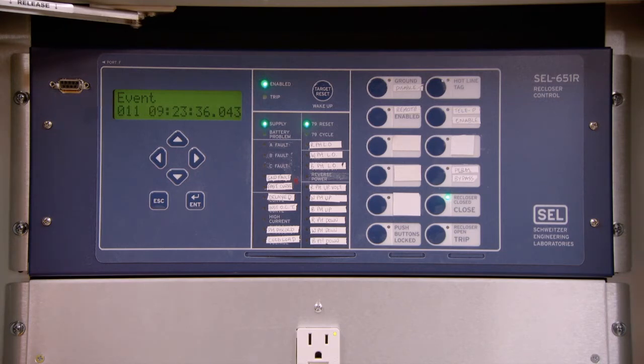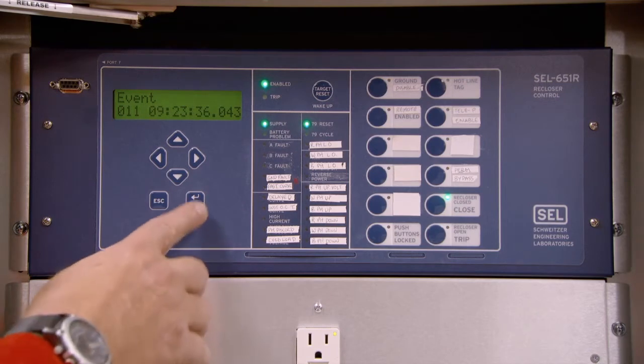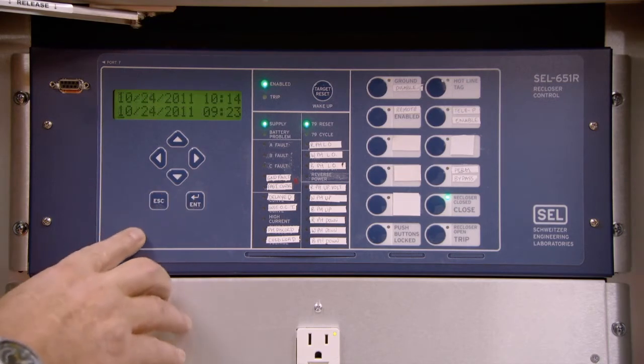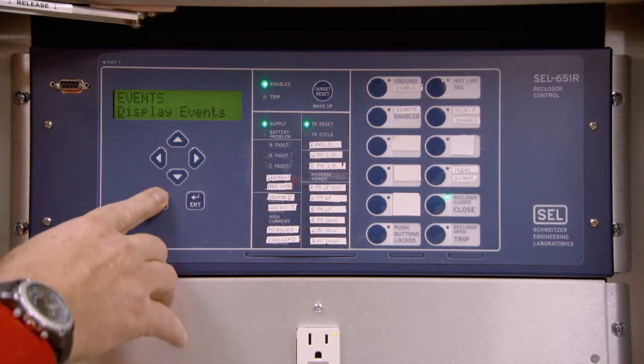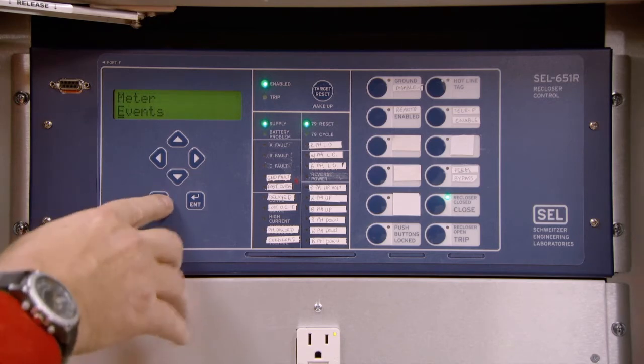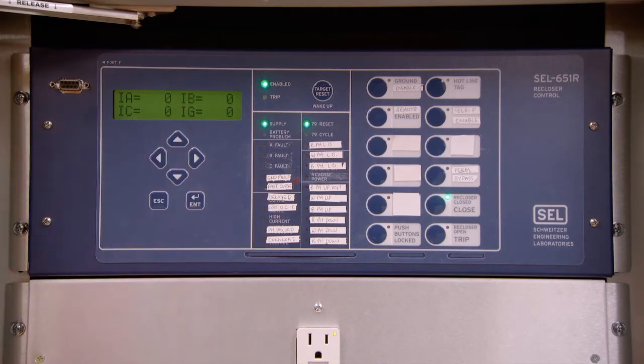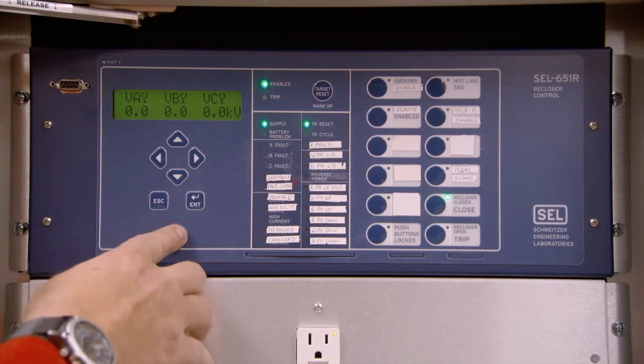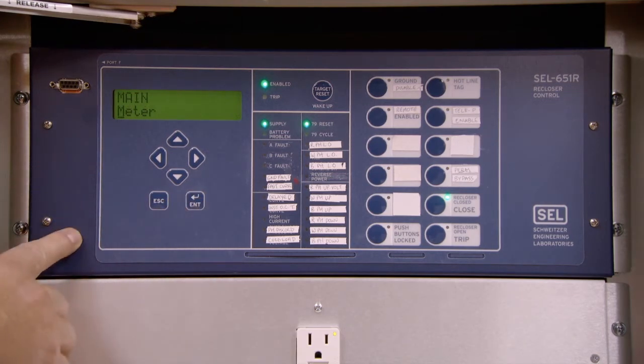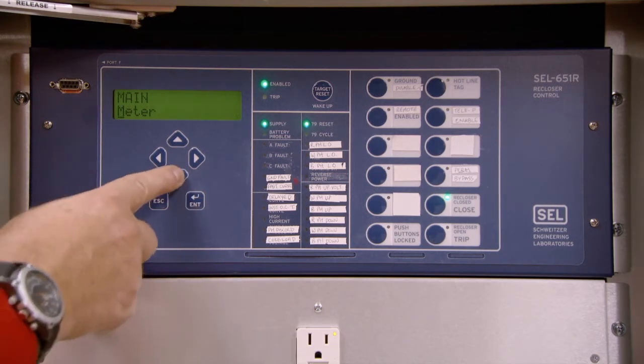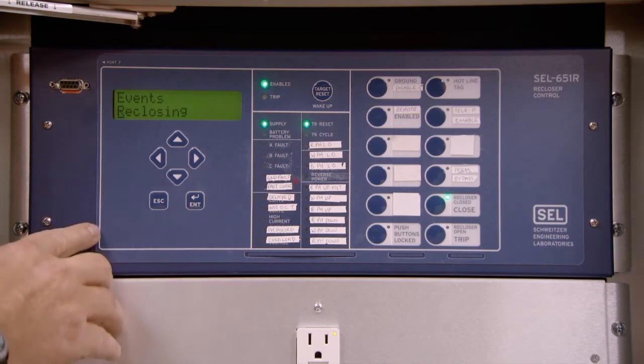An easier way to review this is to have an actual download of the events and histories. But for a quick reference on site, you can go through this manually and examine the individual event displays. To get back to the main menu, hit Escape twice. Now we're back into the main scrolling window. If we press Enter, we are into metering values again. The down arrow takes us to Events, and when pressed again, we arrive at the Reclosing menu.